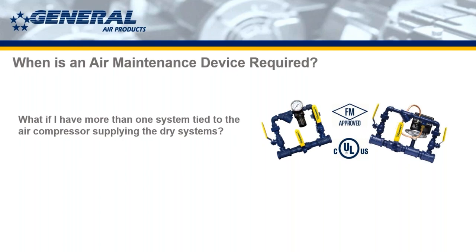That being said, there is nothing that limits the amount of systems that you can put to a compressor. But we recommend no more than 3 or 4 systems per compressor, so that you can realize the full life of the equipment. You know, again, we want to see 10 to 15 years out of all of our equipment, and keeping it to no more than three or four systems is going to help you realize that. If you start putting 5, 10, 15 systems on one air compressor, you can be relatively sure that it is only going to last a couple years at best.